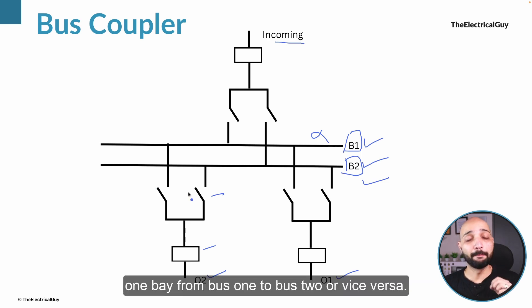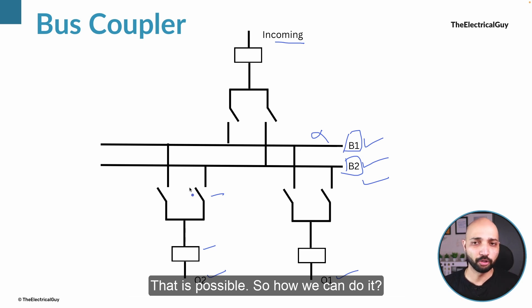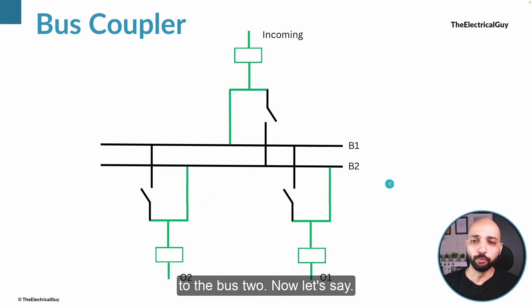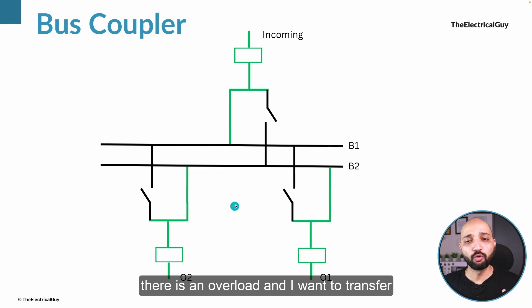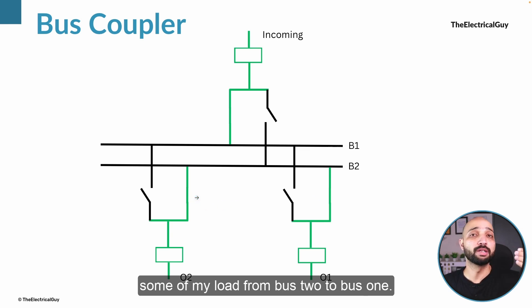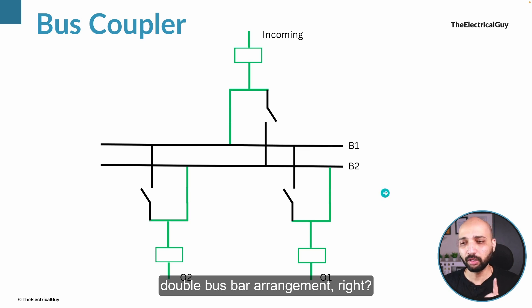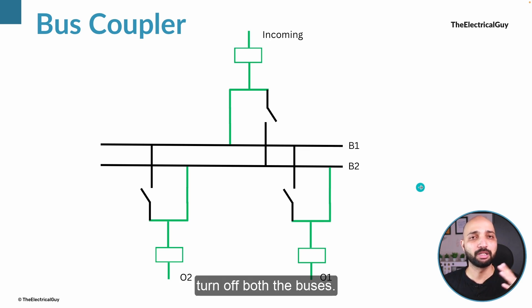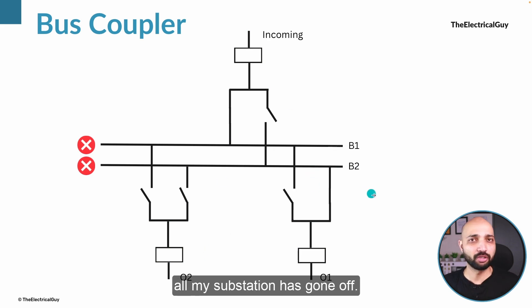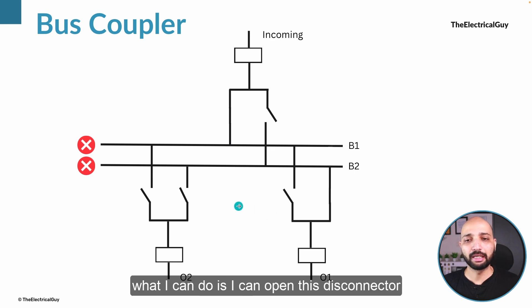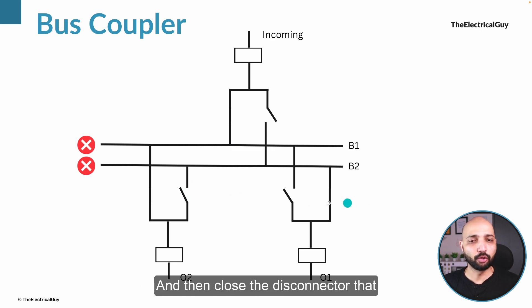Using this arrangement you can also transfer one bay from bus one to bus two or vice versa. Let's say our incoming is connected to bus one and both outgoings are on bus two. If bus two is overloaded and I want to transfer some load to bus one, one way to do it is to first turn off both buses — so there is no supply right now and of course the whole substation has gone off. Then I can open the disconnector connected to bus two and close the disconnector connected to bus one.